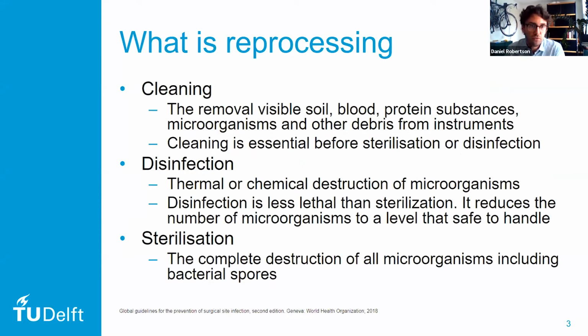So first of all, what is reprocessing? Reprocessing is the whole cycle that happens between instrument use: cleaning, disinfection, and sterilization. Cleaning is defined as actually removing the soil that's left on the instruments after use, and cleaning is the most important step of the reprocessing cycle. Then you have disinfection, which is the thermal or chemical destruction of the microorganisms on the device, but it's less lethal than sterilization.